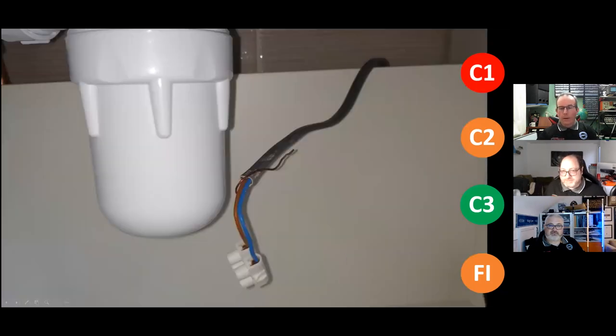Next one. Right, this is a cable with a thing on the end of it. This was in a bathroom, under the basin in the cupboard, directly under the basin. And what we've got there is it was connected and it was live. This is mains power. It's very common that I've seen that in lots of places where an old macerator might be disconnected. Strip it back, connect it to a block, the plumber does it, away you go, puts a new trap on. I've seen it a few times where a supply's been put in there for a macerator, there's a change in design, and the cable's just left there.